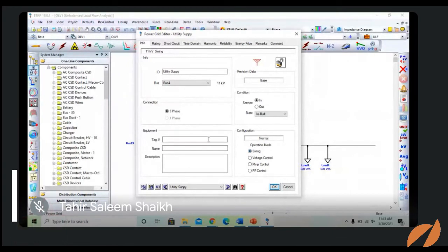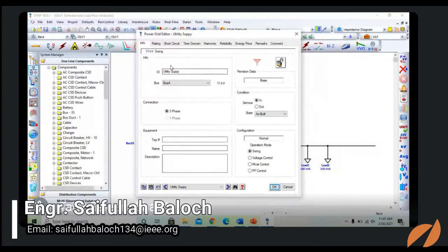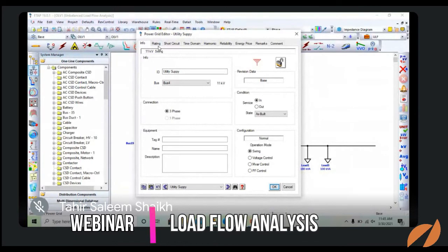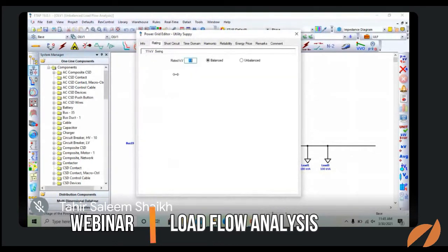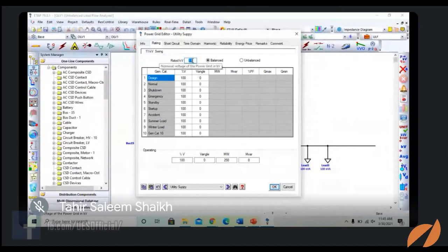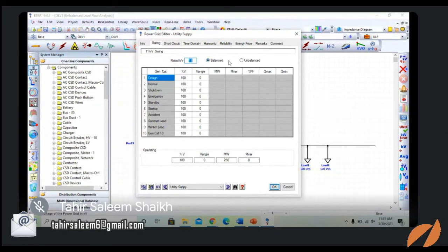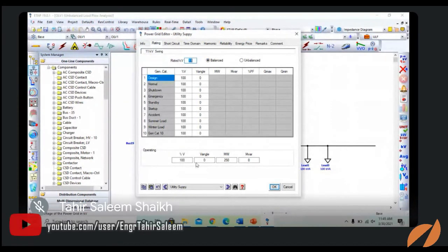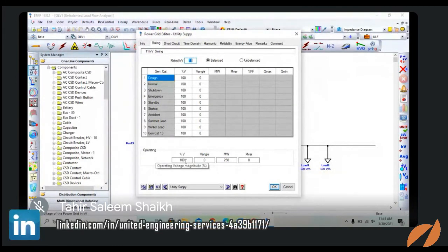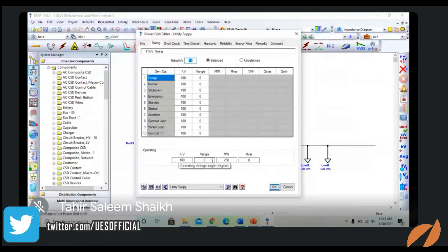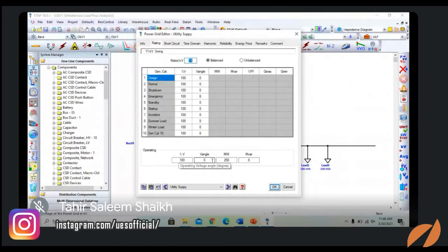Now, if you want to put a tag or name or description, you can also put it right over here. Rating. For the rating, we have a rated kV, and it is a balanced one. Balanced means it has no unsymmetrical parameters in that bus. Operating condition, the voltage is 100%. I will not allow any kind of decline in the voltage in that bus, in that utility. What is the voltage angle? That is the operating voltage angle, which gives you an origin. So I am starting from the origin.